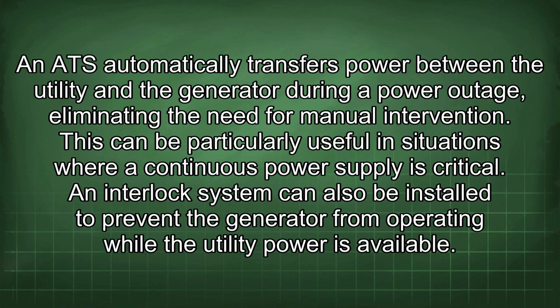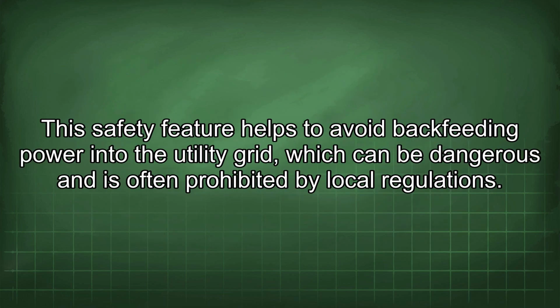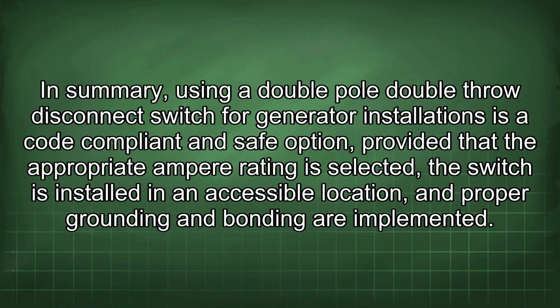An ATS automatically transfers power between the utility and the generator during a power outage, eliminating the need for manual intervention. This can be particularly useful in situations where a continuous power supply is critical. An interlock system can also be installed to prevent the generator from operating while the utility power is available. This safety feature helps to avoid backfeeding power into the utility grid, which can be dangerous and is often prohibited by local regulations.